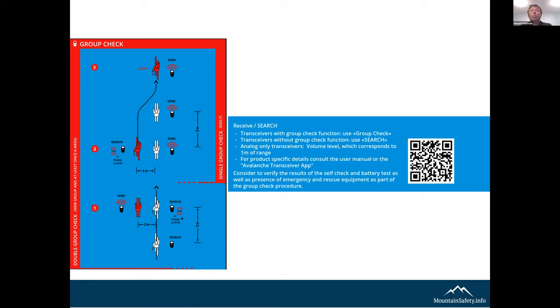What happens when there is a problem on the receiver side, the searching device? When the receiver has a problem, it loses sensitivity, and perceives the signal weaker than it actually is. It then thinks it's at a further distance, so the distance indication goes up. As soon as it's higher than 2.0, it's not within the acceptable range for a passed result. Therefore the group check is negative, and you won't hear a beep for devices with acoustic confirmation.